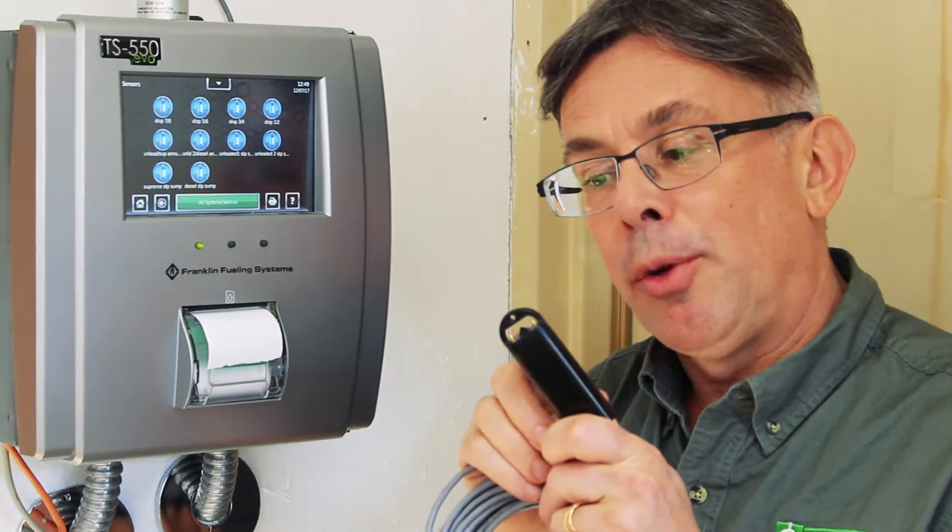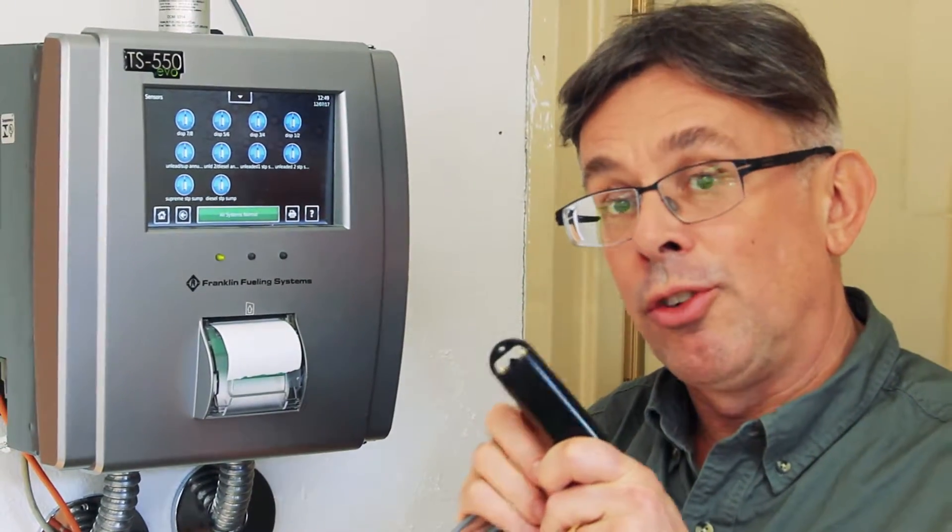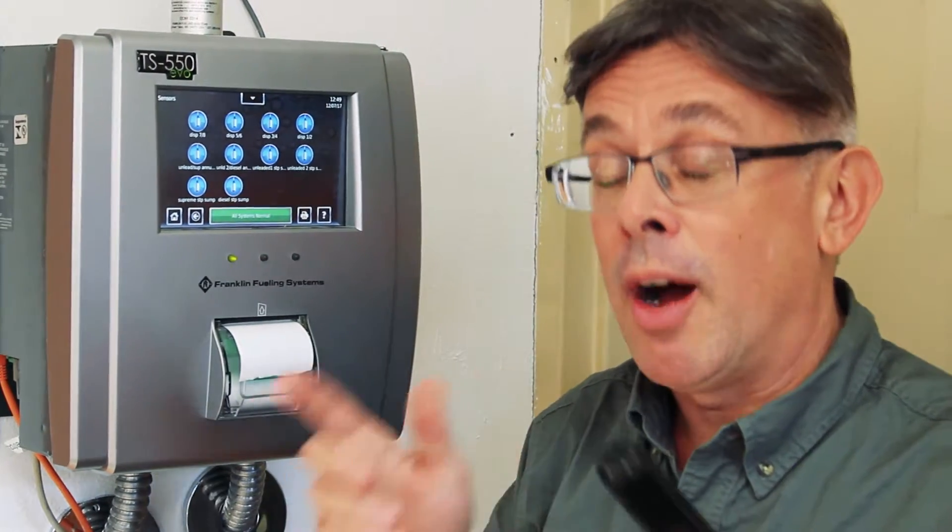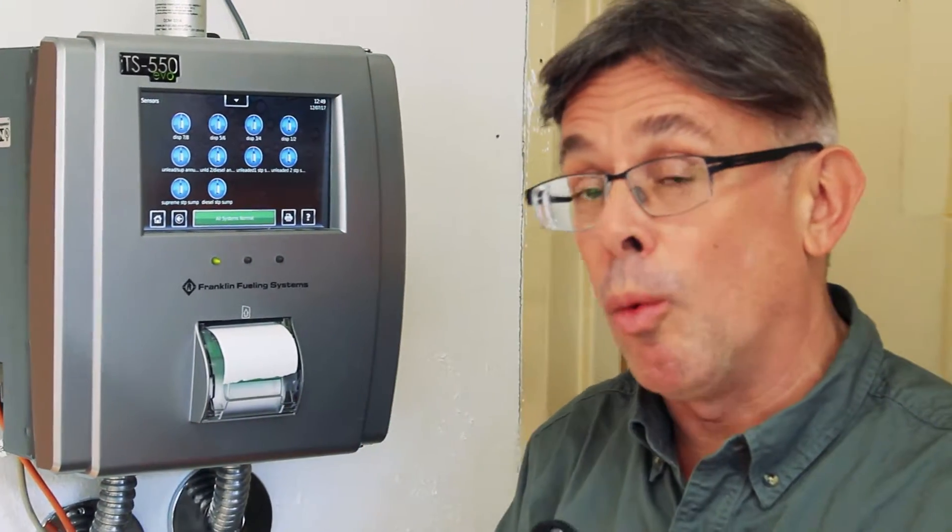These discriminating sensors, these optical sensors that are found in certain interstitial systems, can differentiate between fuel and water. Obviously, fuel is the worst, but even if you get water in your containment system, you'll want to get it out right away.